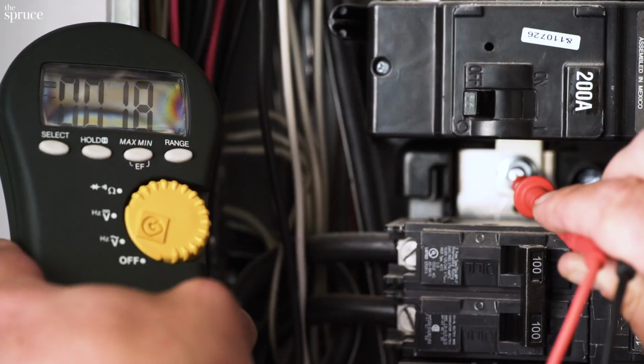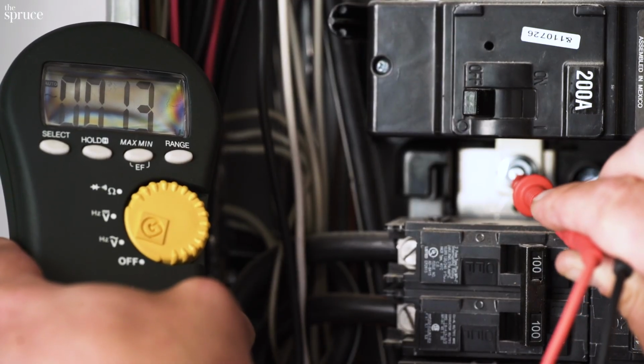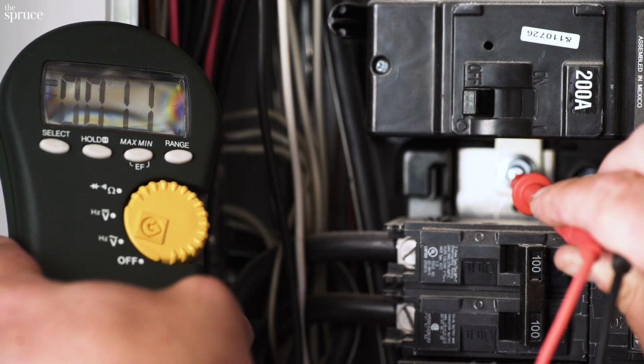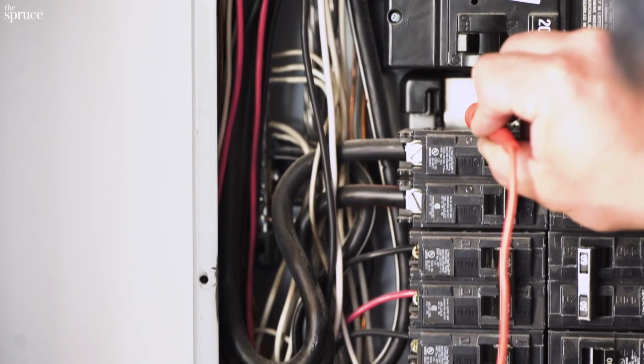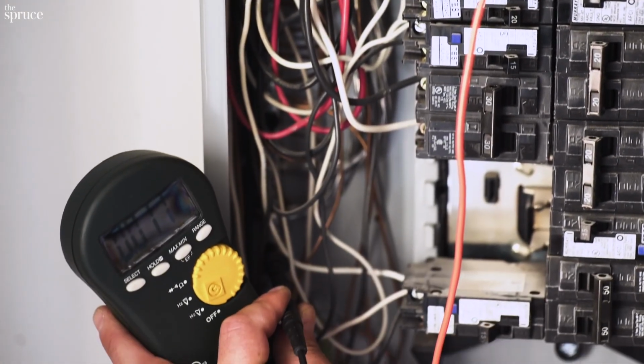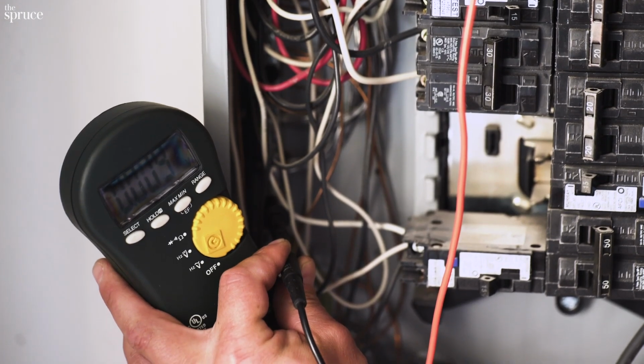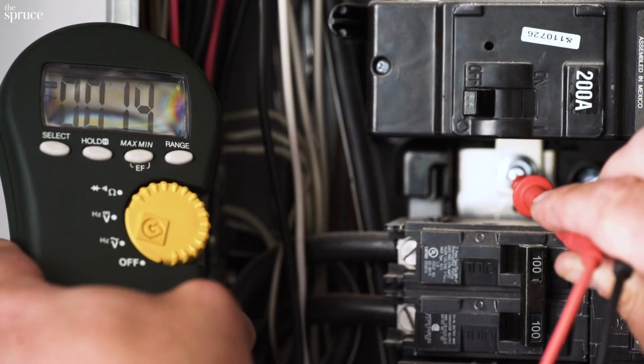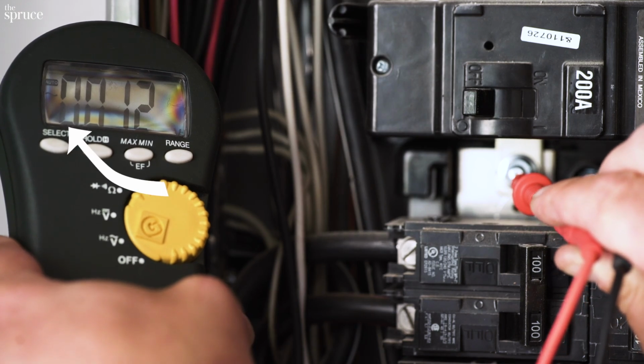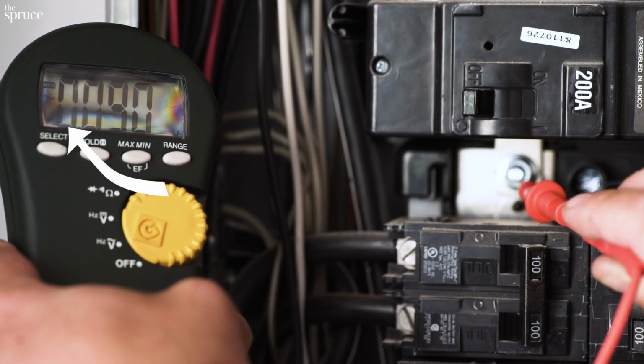It's a good idea to confirm power is off before touching anything in your panel. Use a multimeter or a non-contact voltage tester to check hot wires or any exposed area of either hot bus bar. The tester should not pick up voltage from anything in the panel. Our multimeter is showing less than 1 volt, so we know the power is off.